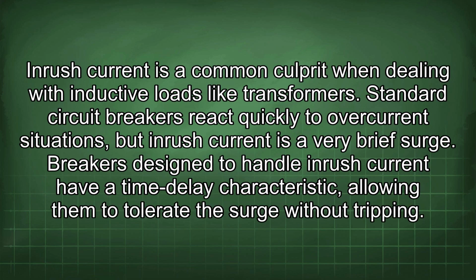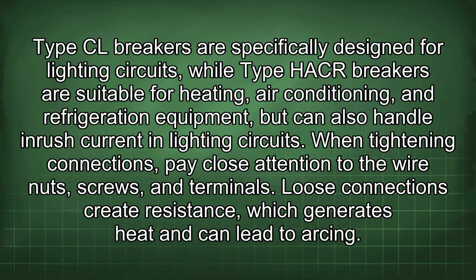Inrush current is a common culprit when dealing with inductive loads like transformers. Standard circuit breakers react quickly to overcurrent situations, but inrush current is a very brief surge. Breakers designed to handle inrush current have a time delay characteristic, allowing them to tolerate the surge without tripping. Type CL breakers are specifically designed for lighting circuits, while Type HACR breakers are suitable for heating, air conditioning, and refrigeration equipment, but can also handle inrush current in lighting circuits.